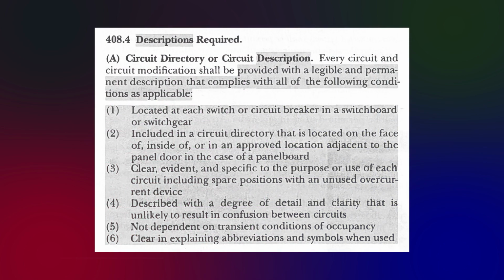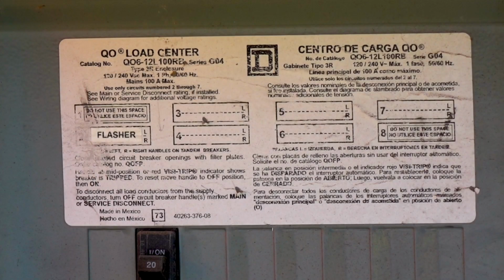The NEC requires that the circuit directory in the load center be filled in with a complete description of the load served by each breaker. The NEC requires that this be done with a permanent ink pen that will not bleed or run if it gets wet. The inspector must confirm the circuit directory has been completed. It is a simple task for the contractor, but is occasionally overlooked.